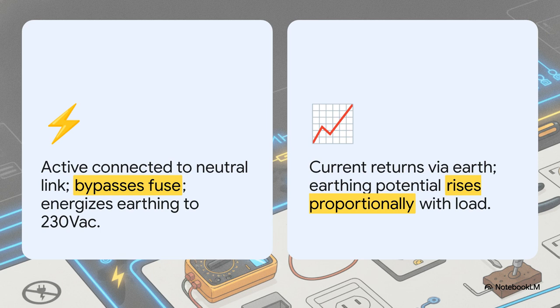Alternatively, we have a high impedance or open circuit neutral. In this scenario, the current tries to return to the distribution system via the earth electrode. So as the installation draws more current, the potential of the earthing system rises proportionally. While one is an immediate shock hazard and the other scales up with the load, both can bypass your standard RCD protections and energize exposed metal parts.